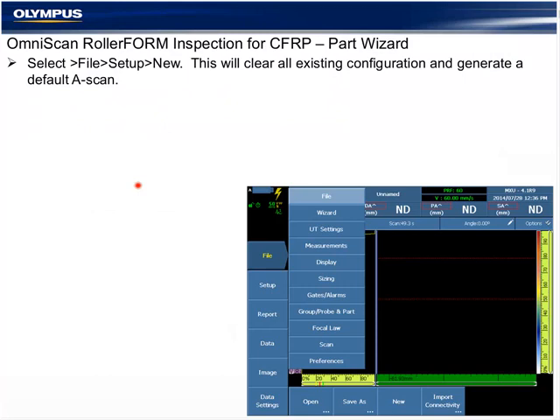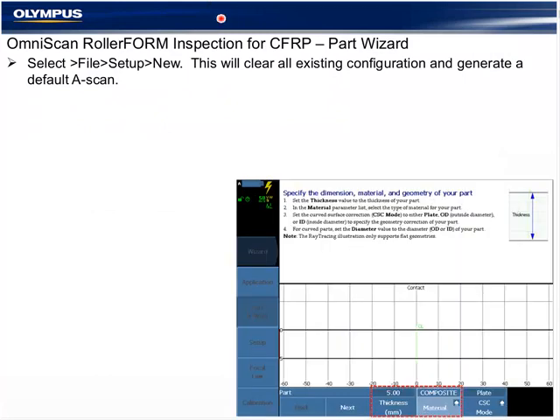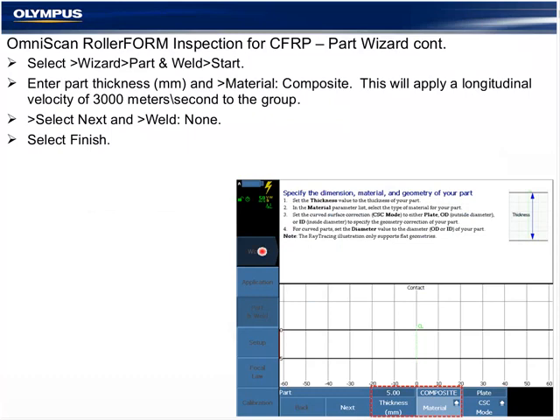So for any application in the OmniScan, to clear out all existing configuration and start with a default blank A-scan, we're going to select File from the main menu and New. This will clear out the group and give us one default A-scan. Then we move into the wizards.